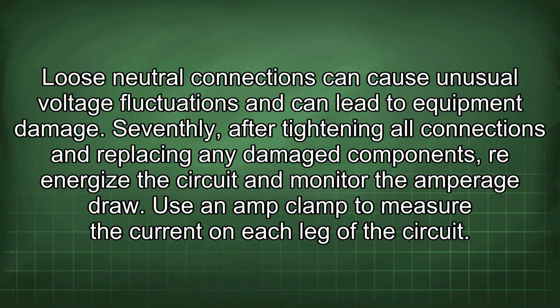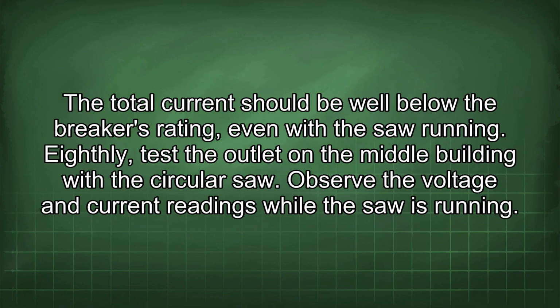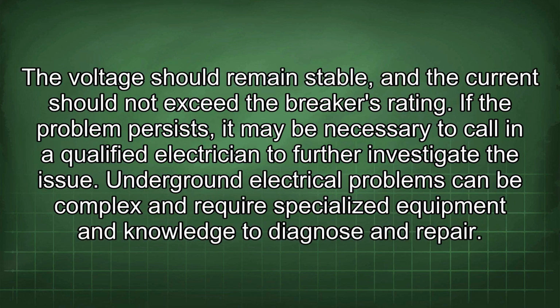Seventhly, after tightening all connections and replacing any damaged components, re-energize the circuit and monitor the amperage draw. Use an amp clamp to measure the current on each leg of the circuit. The total current should be well below the breaker's rating, even with the saw running. Eighthly, test the outlet in the middle building with the circular saw. Observe the voltage and current readings while the saw is running. The voltage should remain stable, and the current should not exceed the breaker's rating.